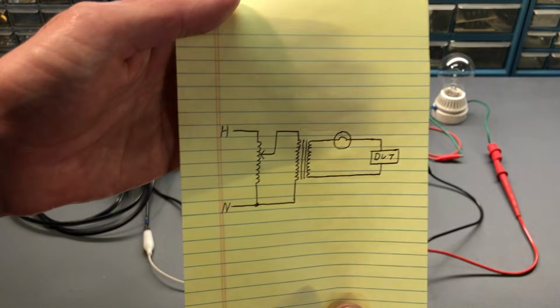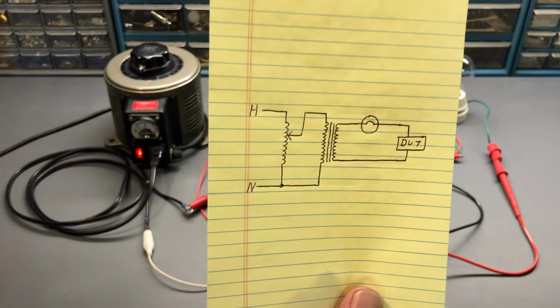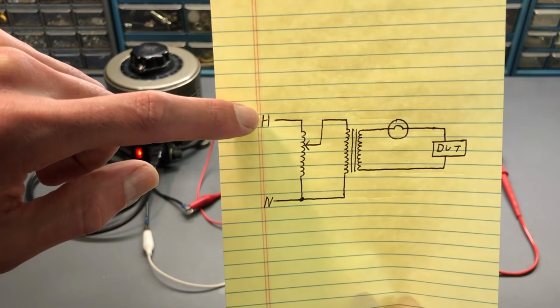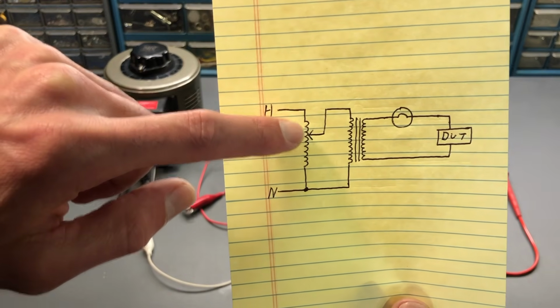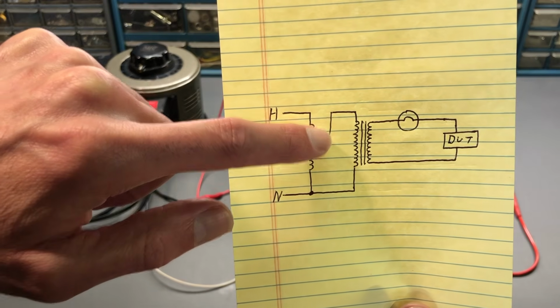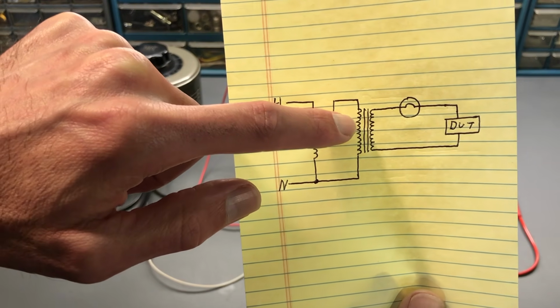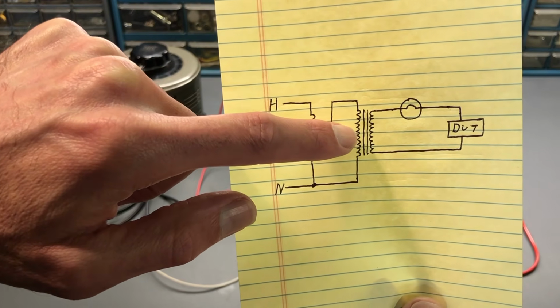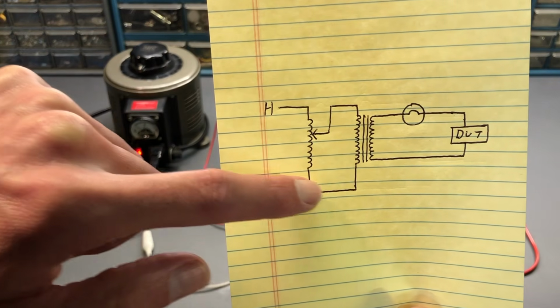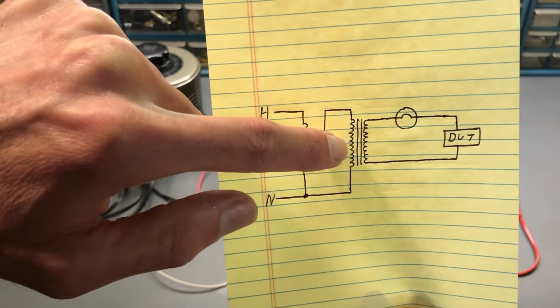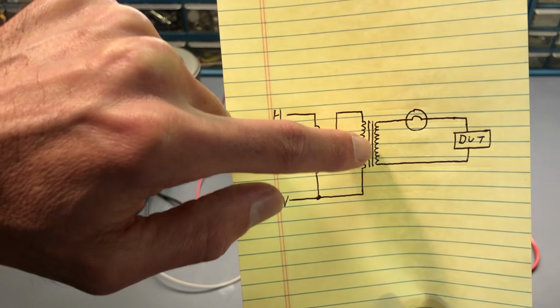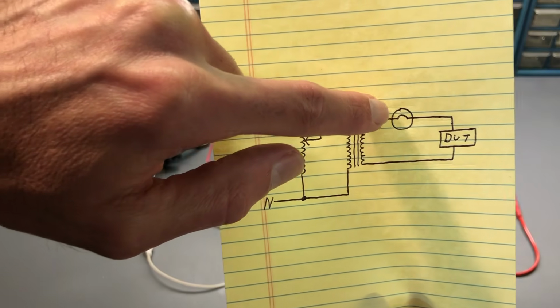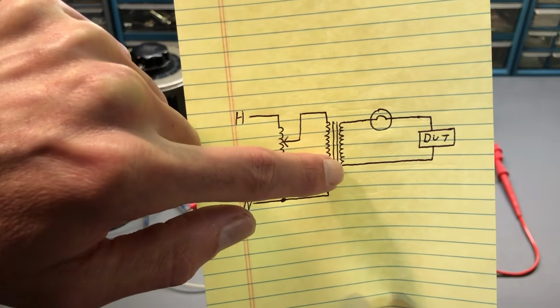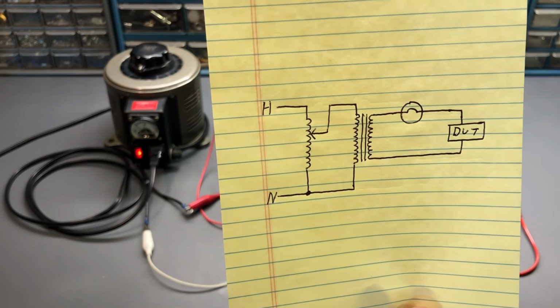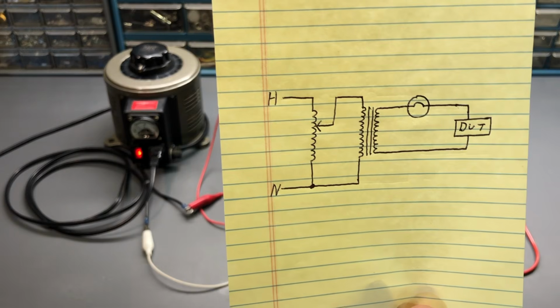So electrically, here's the schematic for what we see in front of us. We have the AC line, hot and neutral, coming in through the Variac. The tap on the Variac comes over here, applies voltage to the primary of the isolation transformer, and returns back to neutral. On the secondary windings of the isolation transformer, it would come through the incandescent bulb, through the device under test, and then back to the other side of the winding on the secondary side. All right.